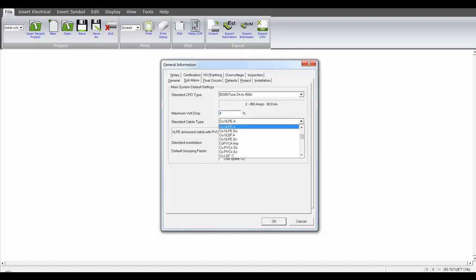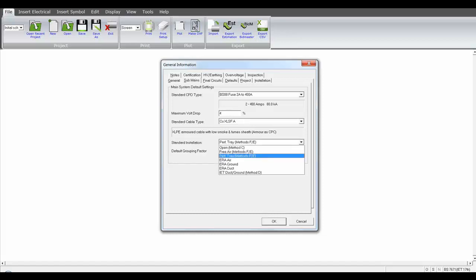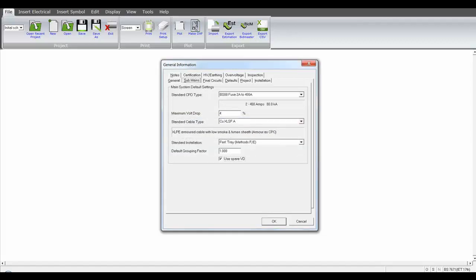This is where we select our preferred cable type, selecting the cable type, and you will get a description of the cable. Standard installation methods based on the regulations are also included for the given cable type. You could apply a default grouping factor at this point if you wanted to, and you can use what we call the use spare volt drop, which will optimize the volt drop and pass any spare volt drop down to final circuits should you have short submains, very long final circuits where the chances are that the final circuits might not reach the voltage drop requirements. So you can actually swap the voltage drop between, and it's the same with the final circuits. You've got the use spare volt drops, so you can optimize the voltage drop between boards. Final circuits is the same.